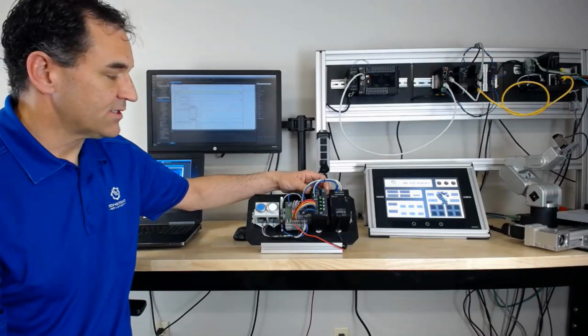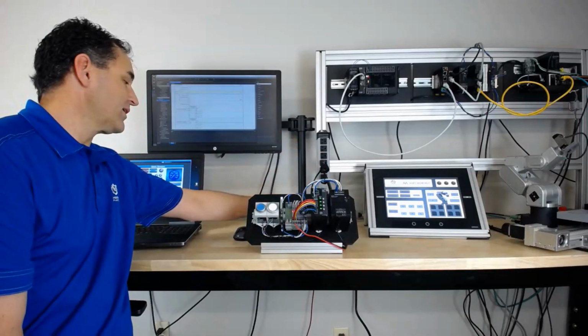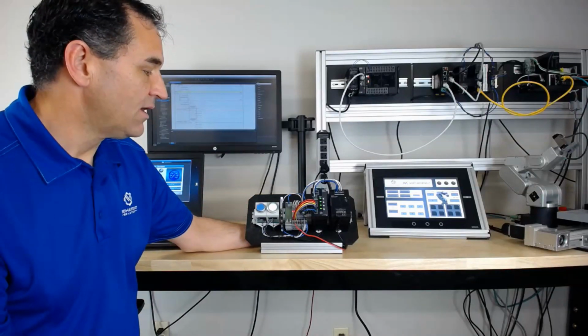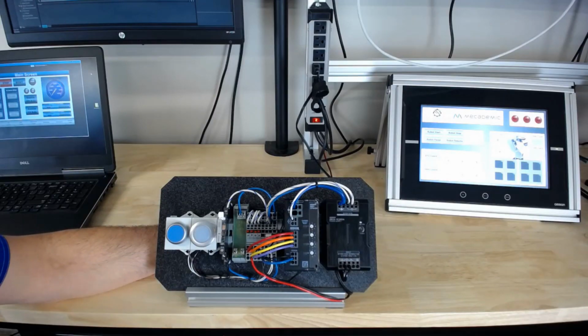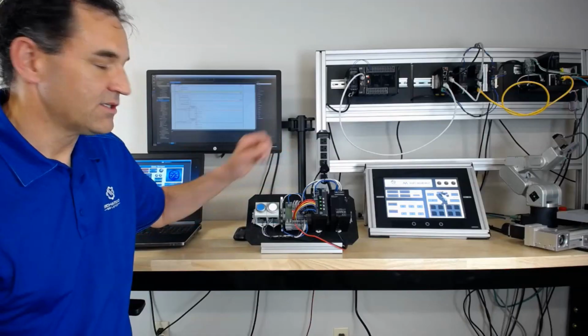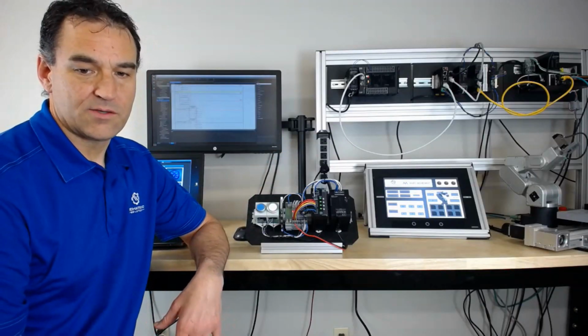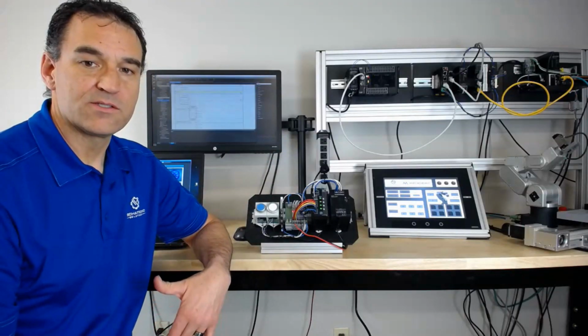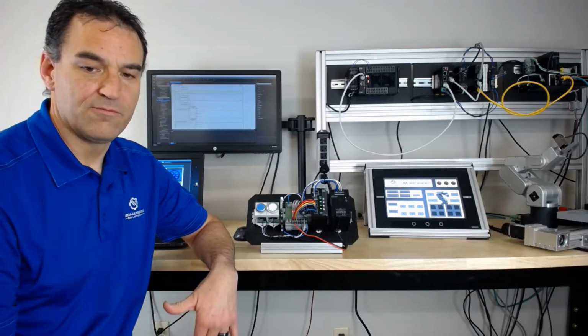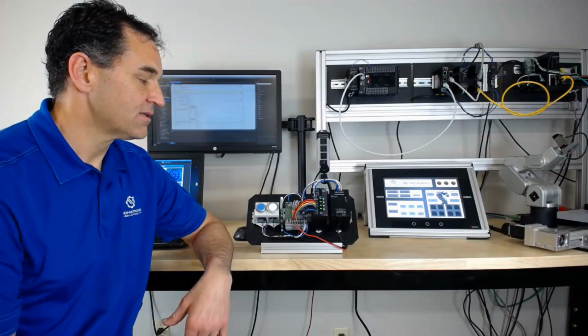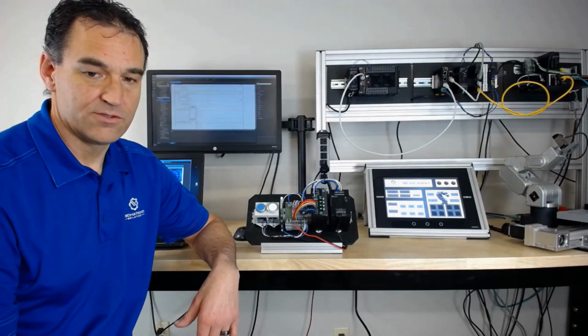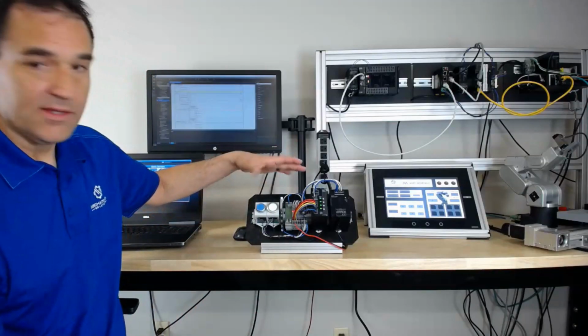It has a sequential startup, so if I cycle power on this, what you'll notice when I turn it back on is we'll have a sequential startup on each of the 4 channels. That sequential startup is actually load dependent, so it can vary from 50 milliseconds up to 5 seconds, depending on the load on each individual circuit.